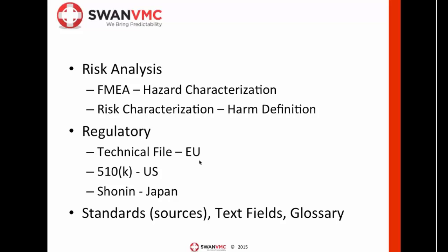And then the risk analysis people simply have to link them to the risk analysis work items that are applicable, and then all the calculation for the RPLs and the harms and the harm severities happens automatically. And so it really saves a lot of time if we don't have to sit there and take those FMEAs and reprocess them into the overall risk management file.